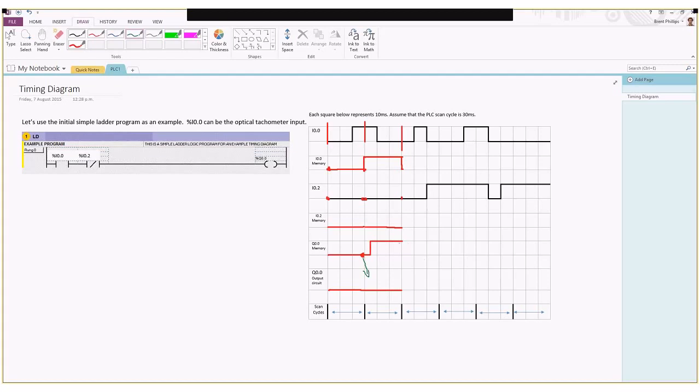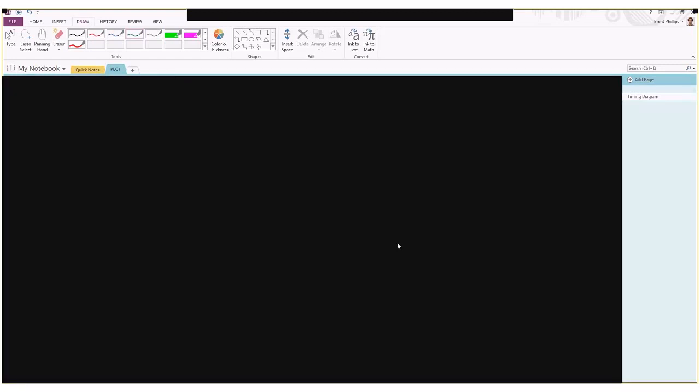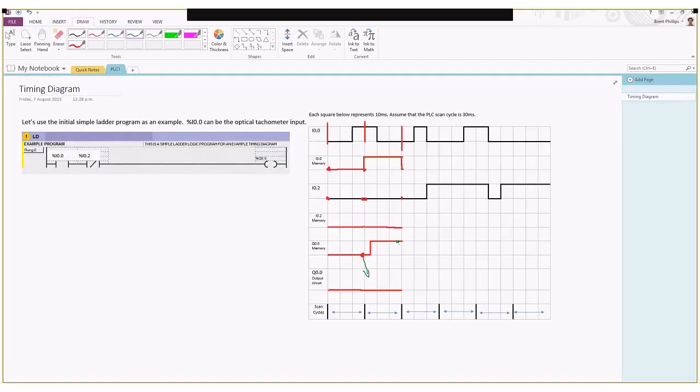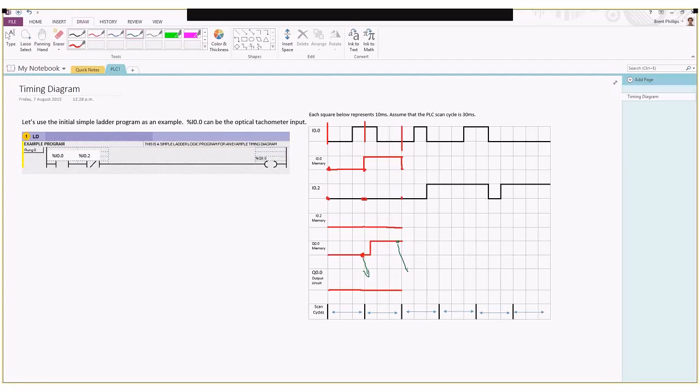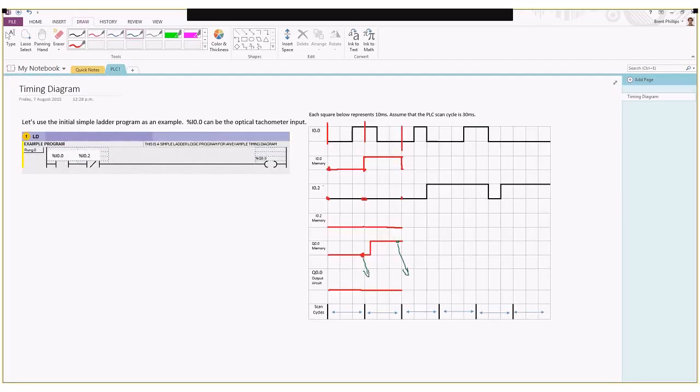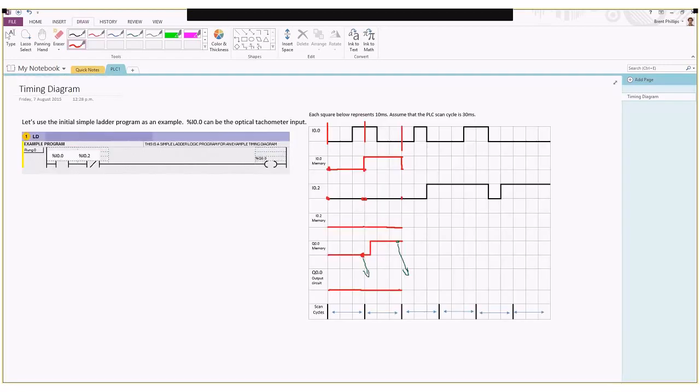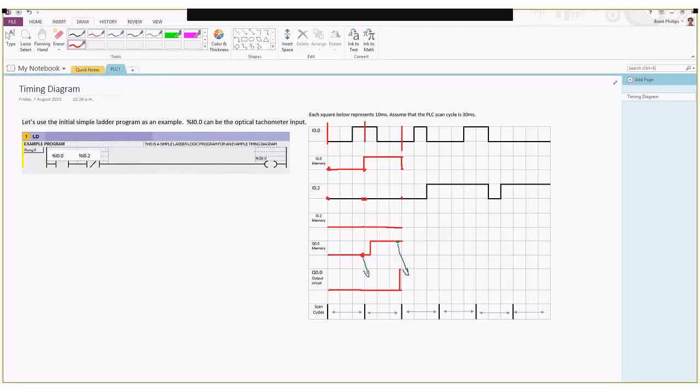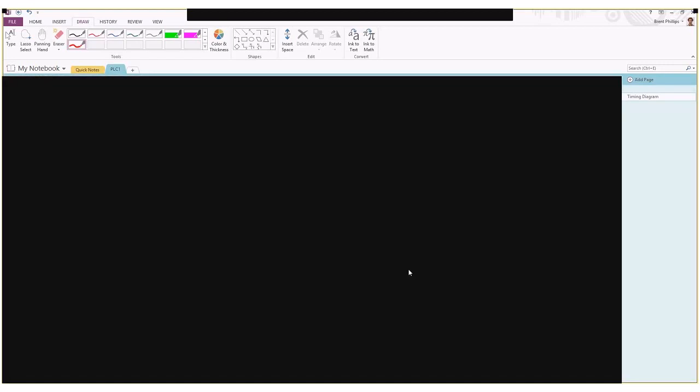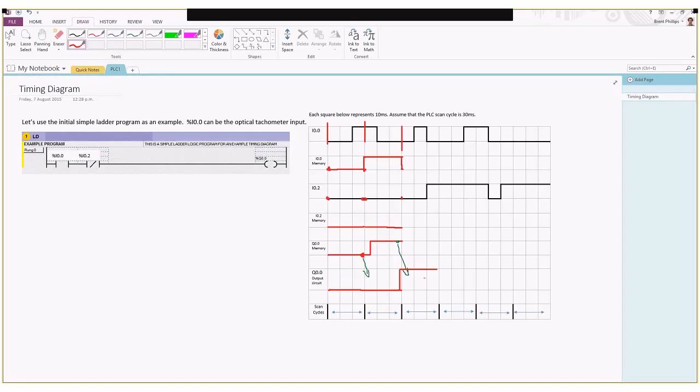If we do the same thing for the last part of our second scan cycle where the memory has turned on, that's going to flow through to be the state that our physical output uses for the following period of time. It's going to be just the end of that second scan cycle around here. One of the last things that the PLC does, it's going to turn on that and hold it on for the entire remaining scan cycle.